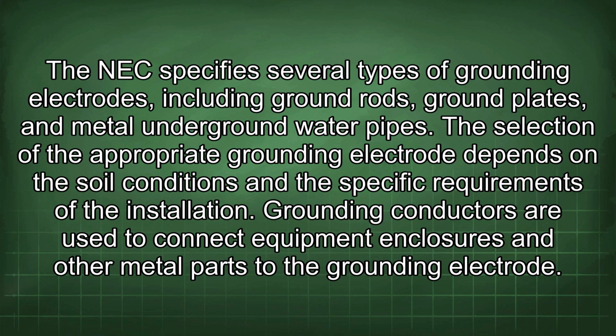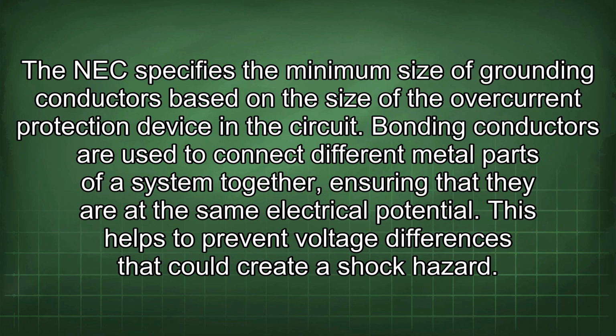Grounding conductors are used to connect equipment enclosures and other metal parts to the grounding electrode. The NEC specifies the minimum size of grounding conductors based on the size of the overcurrent protection device in the circuit. Bonding conductors are used to connect different metal parts of a system together, ensuring that they are at the same electrical potential. This helps to prevent voltage differences that could create a shock hazard.